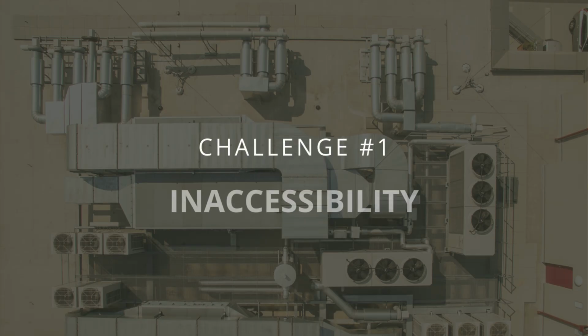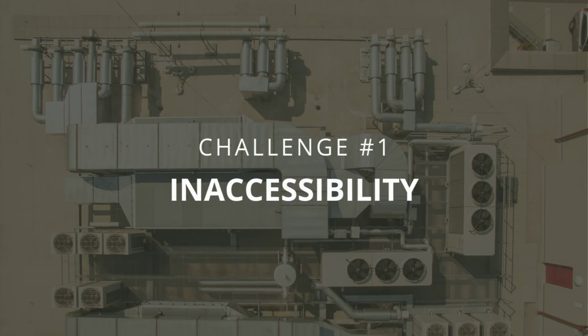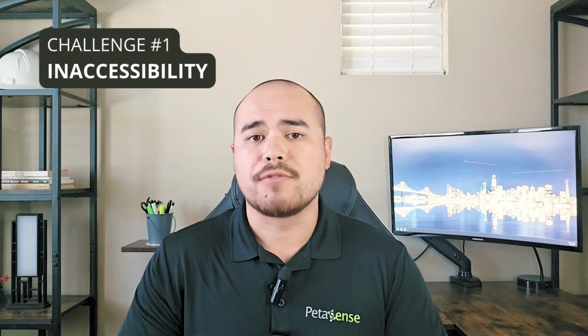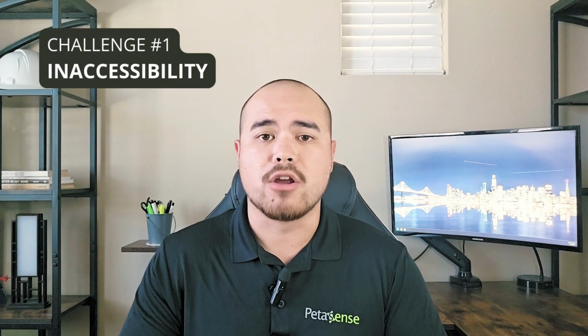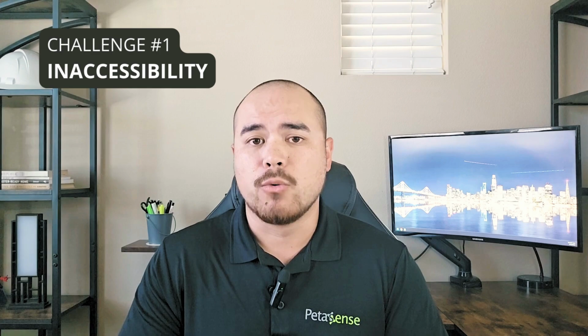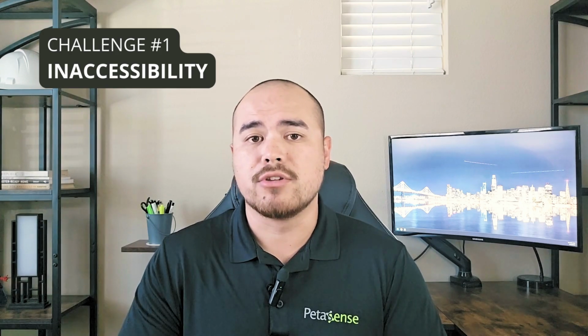Monitoring air handling units comes with a unique set of challenges. Here are the primary issues we've encountered and how to overcome them. Challenge 1. Inaccessibility. AHUs are often fully enclosed and located in hard-to-reach areas. This makes it nearly impossible to access key monitoring points like the bearings while the machine is running. And trying to place a wireless sensor inside the AHU usually doesn't work out, as the metal housing and internal obstructions often block wireless signals from getting in or out.